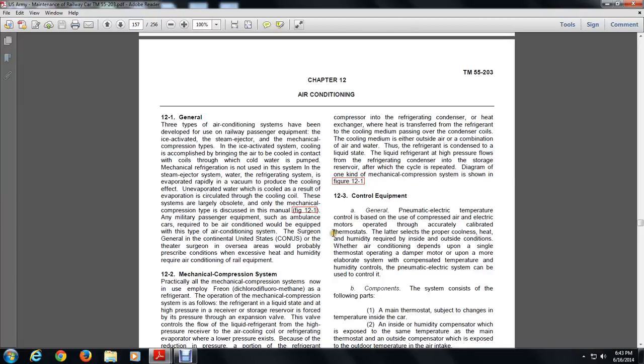Chapter 12: Air Conditioning. Three types of air-conditioned systems have been developed and used in railway passenger equipment: ice-activated, steam-ejector, and mechanical compression. The ice-activated system accomplishes cooling by bringing air into contact with cool water that is pumped through the system; mechanical refrigeration is not used. The steam-ejector system uses water evaporating rapidly in a vacuum to produce cooling, with the un-evaporated water cooled by evaporation and circulated through the cooling coil. This system is now largely obsolete.